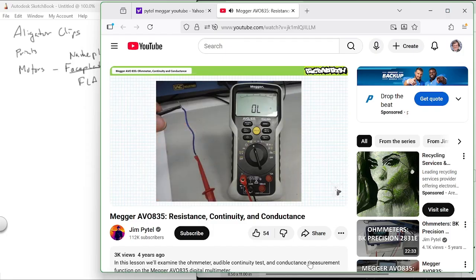However, the ohm meter reveals a dark secret: this wire is in fact broken inside the insulation, and no conductive path exists from end to end. An ohm meter works for these types of checks. However, there's a better way to perform a continuity test. In addition to the numerical measurement of resistance, the AVO 835 offers an audible continuity test.